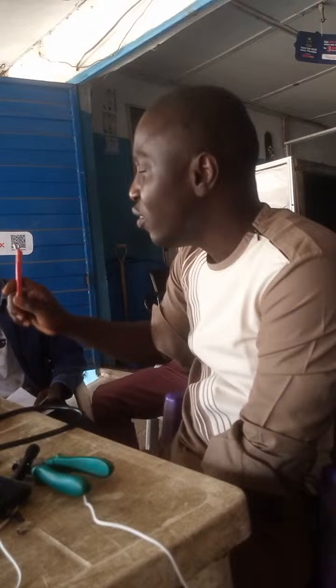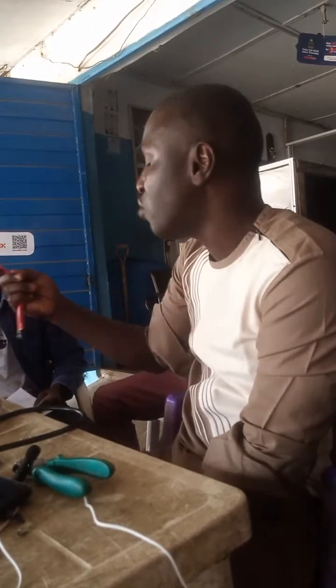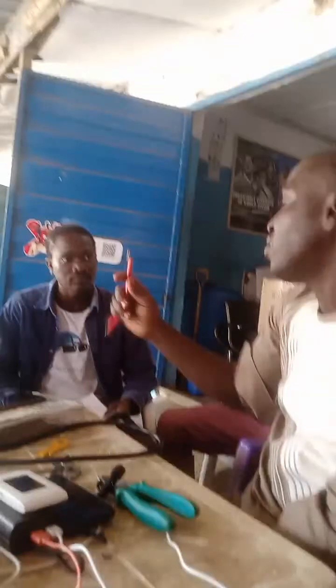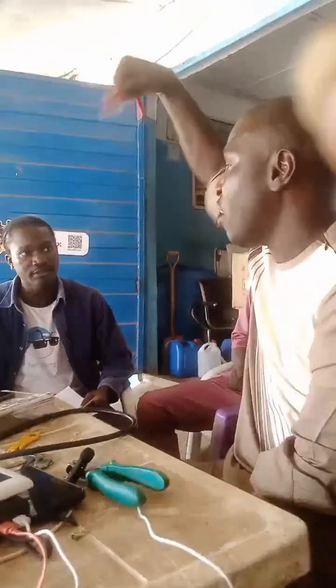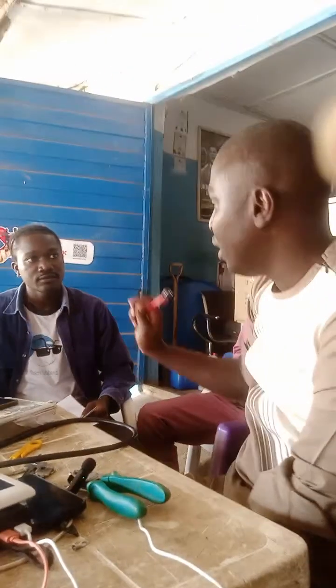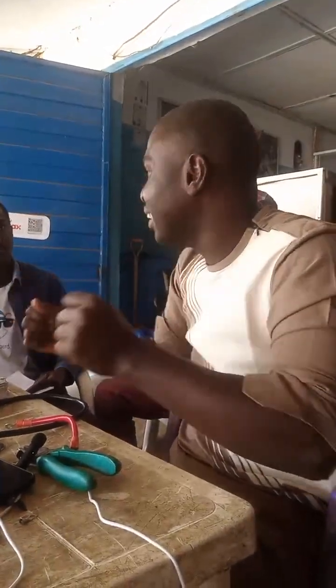For those batteries that are a far distance apart, you can use a lesser size of cable. It has its own calculation, but instead of using 25 mm, you can use 10 mm cable to loop those where we have small loops together. You don't need a special calculation for that, but the one carrying the bigger current you must be sure of the standard.